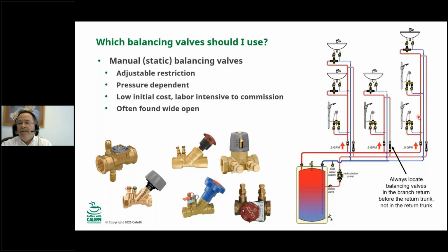And if you look over here in the schematic, always locate balancing valves here in the return. Okay, here's the supply trunk. There's the supply that goes out to the fixtures, and this return right here, somewhere in this line, is where the balancing valves go before these pipes tee into the return trunk that goes back to the recirc pump. That way the balancing valve is controlling the flow for the set of fixtures where it's located in that group of fixtures in that riser.